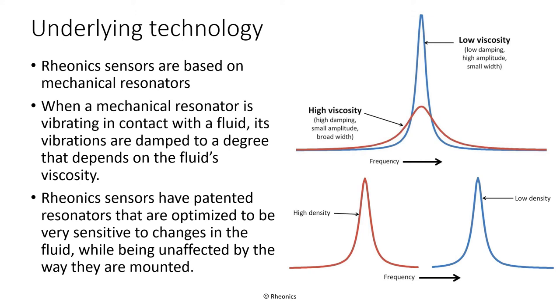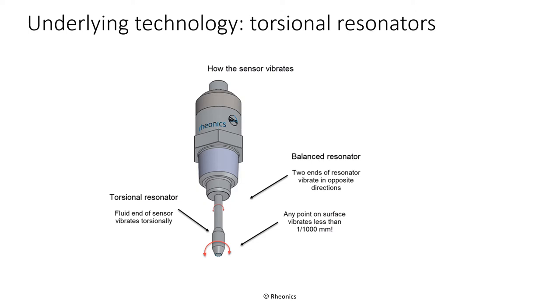Rheonics sensors have patented resonators that are optimized to be very sensitive to changes in the fluid, while being unaffected by the way they are mounted. The SRV, SRD, and DVP all use resonators that vibrate in torsion. Torsional resonators are much better isolated from environmental influences than transverse resonators. Resonators that vibrate transversely, like a tuning fork, tend to be more influenced by how and where they are mounted. Rheonics torsional resonators do not rotate — they measure through microscopic vibrations that are influenced by the fluid's properties. The actual surface motion is less than one one-thousandth of a millimeter.